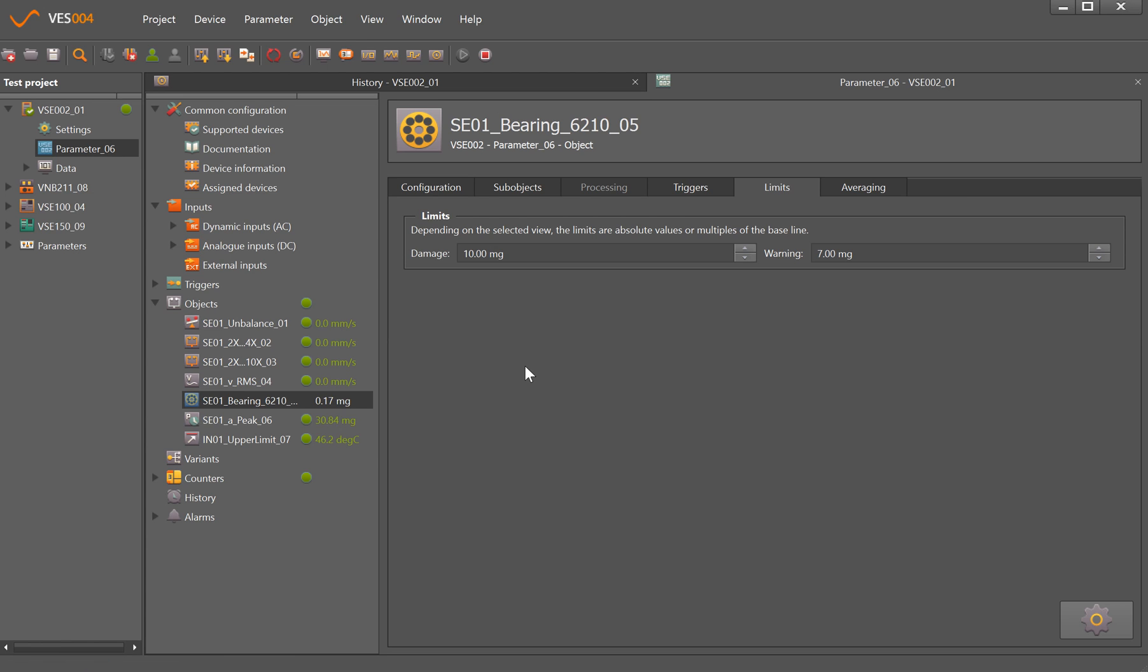So that's really what you need to be doing if you're looking to change alarm levels as time goes on. And we would recommend that once the initial commissioning of a machine has done, you maybe let it run for a few weeks, a month, and then come back and have a look at the history trends for each of the parameters that have been set and then make the decisions on where the alarm levels should be set going forward. But normally a month's worth of data is more than sufficient to give you a good idea of how the machine runs under different conditions, and then you can set the alarm levels correspondingly.